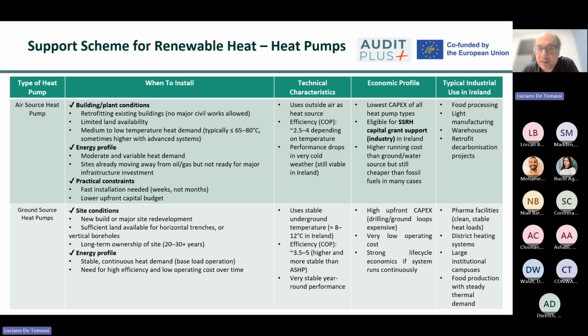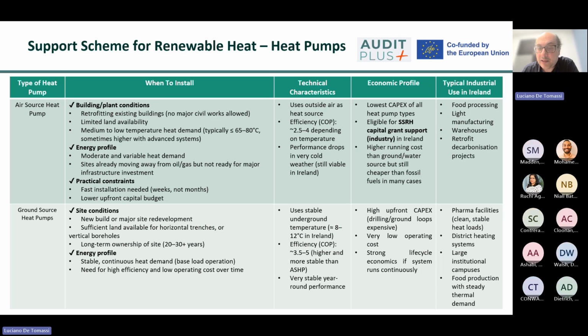Their performance is influenced by outdoor air temperature, which means efficiency typically decreases under colder periods, leading to higher electricity consumption in winter. Despite this limitation, air source heat pumps are relatively simple to install, require minimal site preparation, and do not depend on specific geological or water resources, making them the most practical solution for constrained or urban sites.